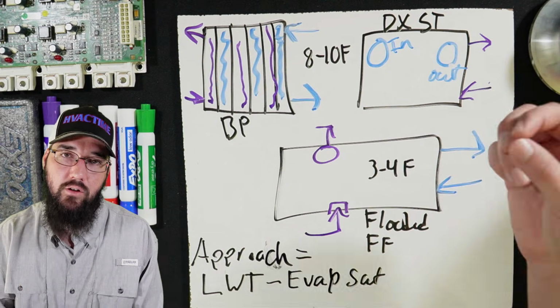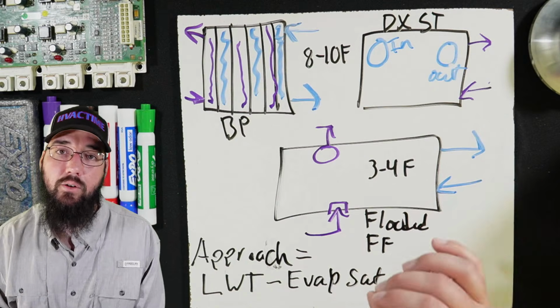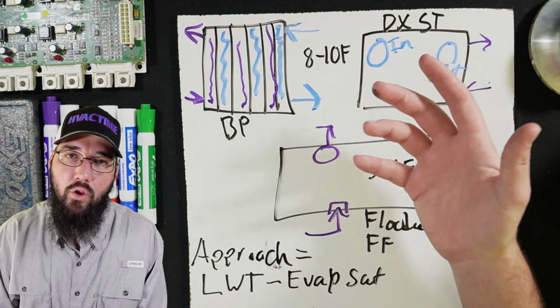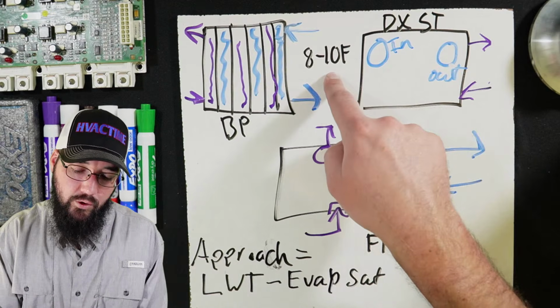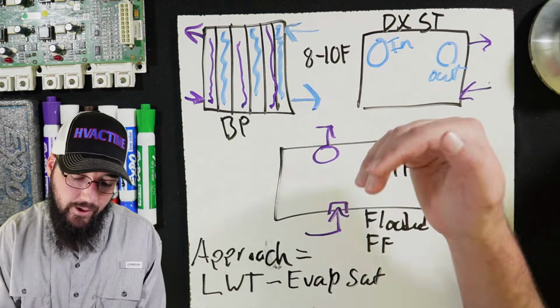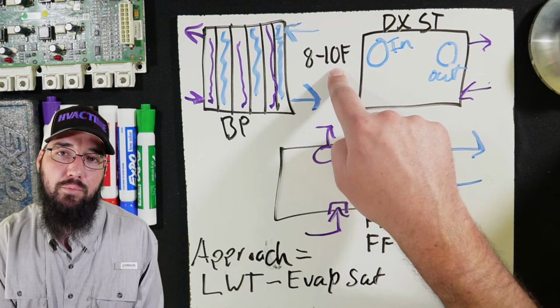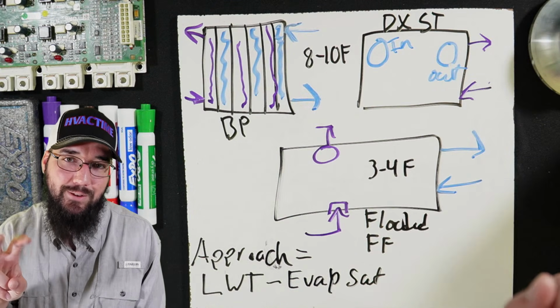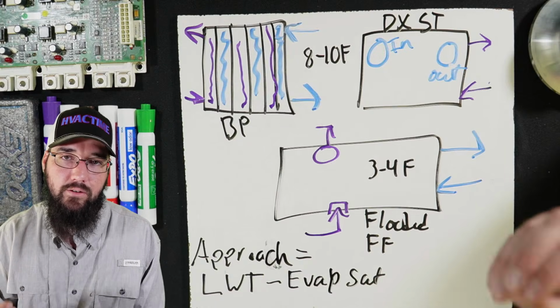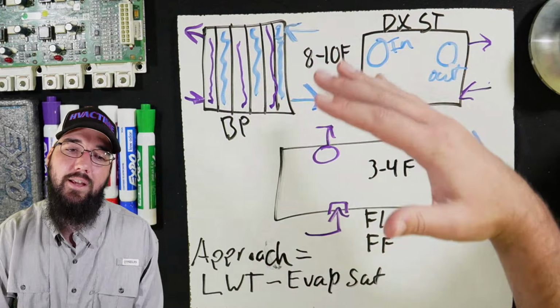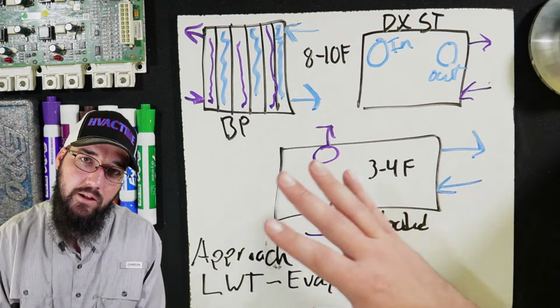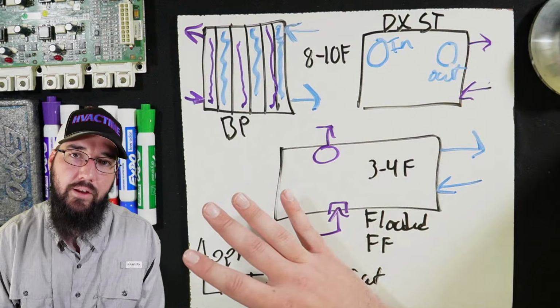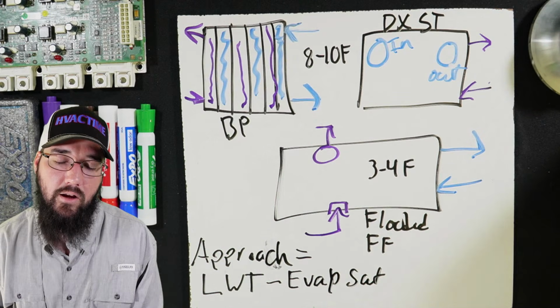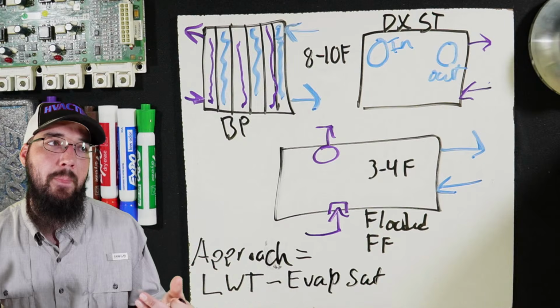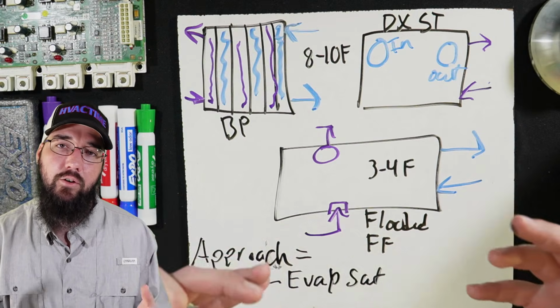So those are things you can look for, and that is where experience really comes in, because if you don't know that, then you could be heavily unloaded or derated, but yet still running high approach value, but it's still within specification. Okay, don't let that trip you up at some point. Understand that these numbers all work together and they fluctuate together. As the machine derates, these numbers should also follow that trend, and they do the same thing as they come back up. Same thing with like the motor current on a compressor.